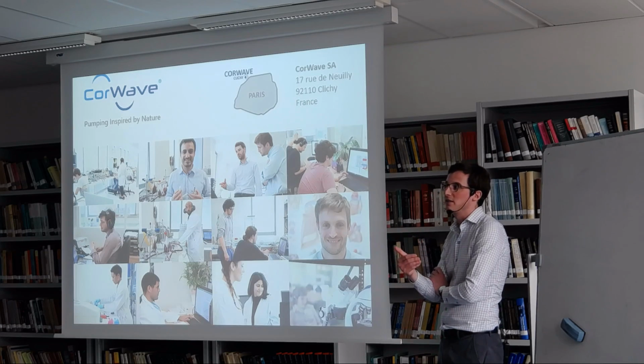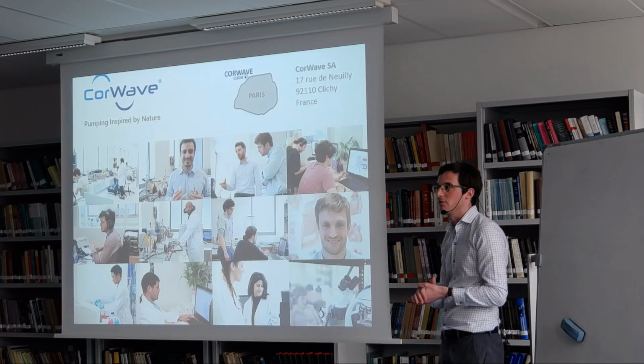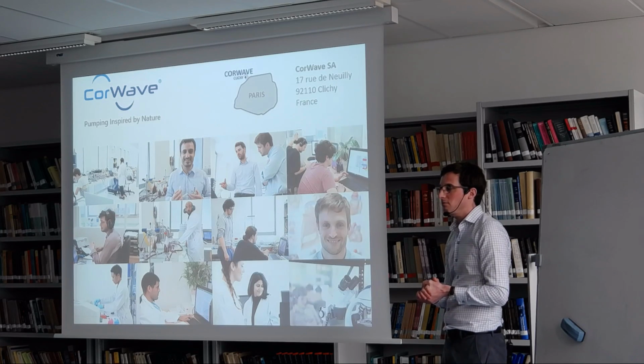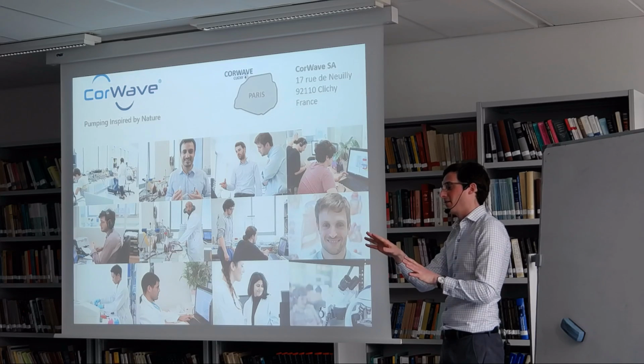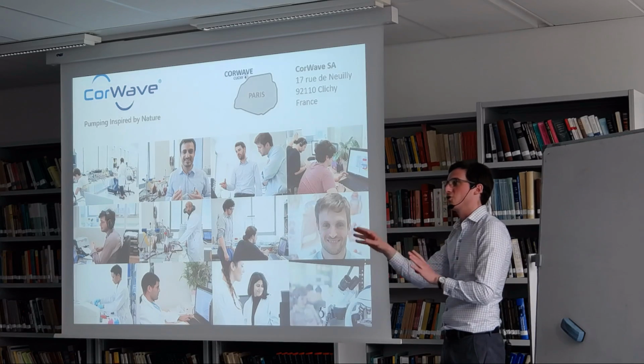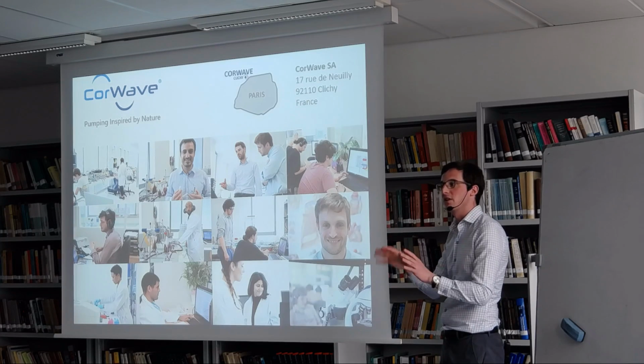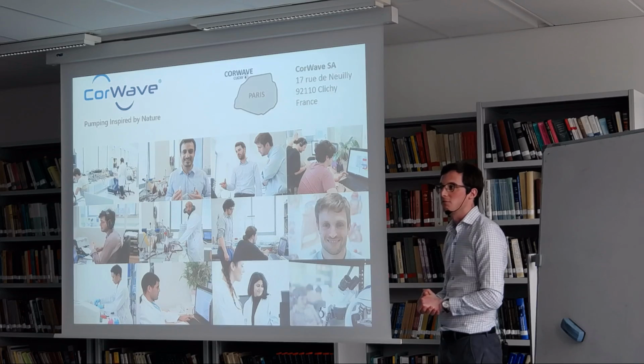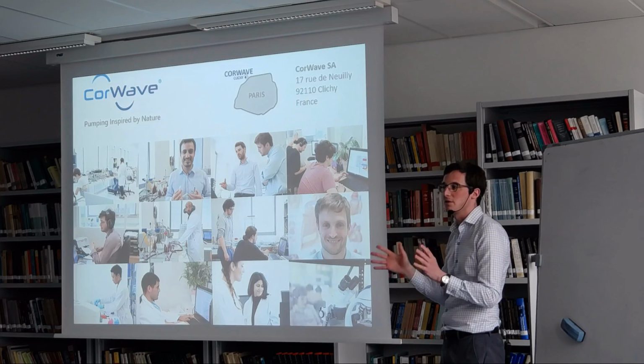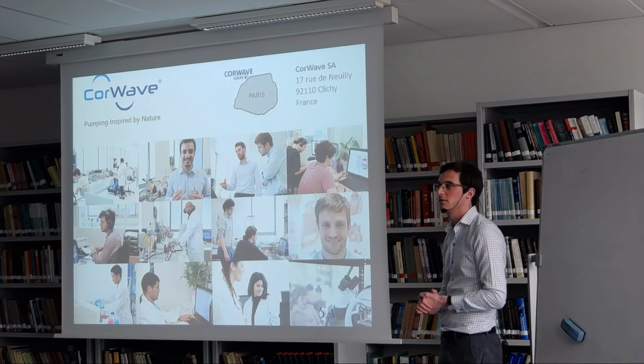And this we clearly see. All the other devices also see it as well. It's basically you change the hydraulic load. So that's one way to do it without introducing an additional sensor, which one would want to avoid. There would be another approach, a bit more complicated, which would be synchronizing the device to something like a pacemaker, which triggers the beating of the heart. That would be the other approach. But typically the approach is to use the signal which is on the electrical signal. Thank you.